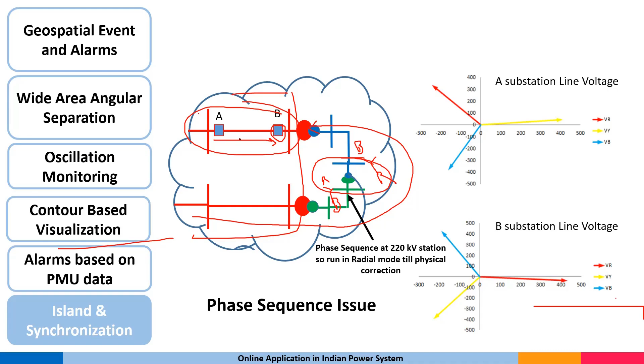This particular issue was resolved when we were trying to synchronize this particular line through this breaker. So here it is R Y B, the same as before. However, if we are charging up to this point, it has converted to B Y R. When you compare this B Y R to R Y B, this information was available, and this particular issue was avoided in real time, and the state was informed to correct the phase sequence fault at the substation level.